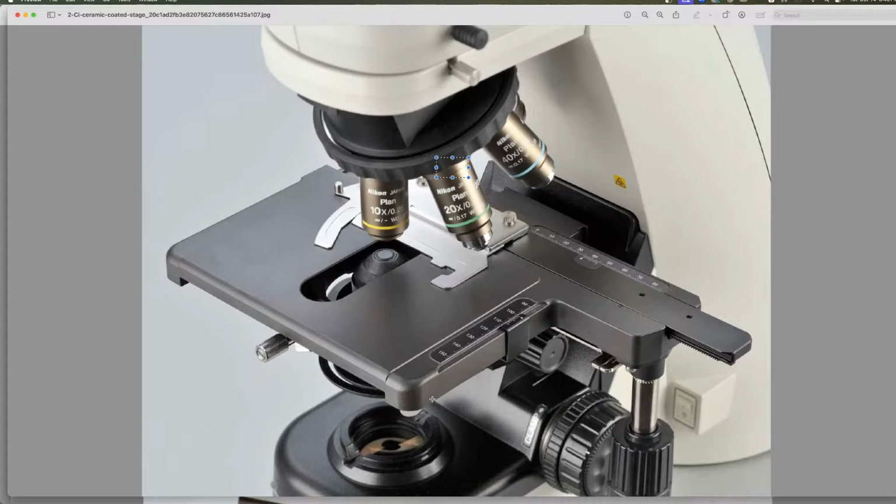And when you do that, think about it, you reopen the diaphragm and you get visible light coming through. You have just lined up the light for the whole microscope, so that when you look through the eyepieces, it's also going to be perfectly aligned to give you evenly lit, bright, high contrast images with no glare or hot spots. The bad news is you really have to do this every time you switch from one objective to another.